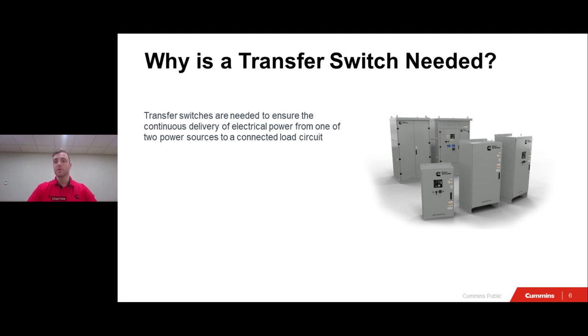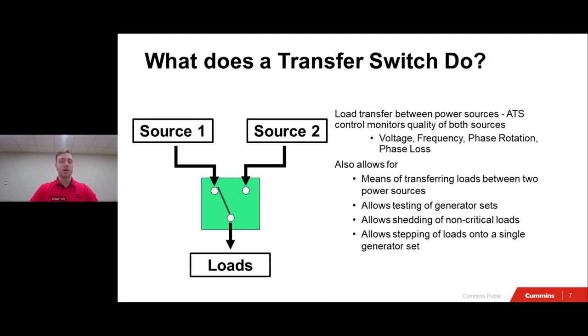So now that there's a little bit of an understanding of why a transfer switch is needed, let's focus on what a transfer switch does. A transfer switch transfers power between two sources. Typically, this will look like an automatic transfer switch transferring power between a normal source, which would be your utility in many circumstances, to an emergency source during an outage. That emergency source most likely being a backup generator, which would look something like this.